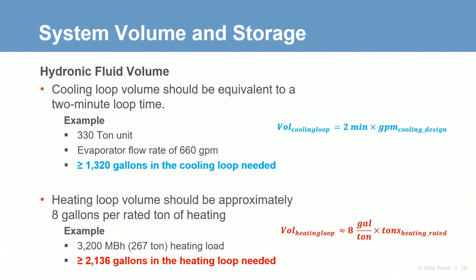This calculation should be made using the rating heating capacity of the largest unit in the system at the AHRI conditions of 120 degrees Fahrenheit leaving hot water temperature and 47 degrees Fahrenheit outdoor air temperature. Using the example system Dan shared earlier, we see that the heating loop volume is substantially larger than the cooling loop. Volume tanks can be used in the production plant to partially meet this need, as shown in the previous configurations.